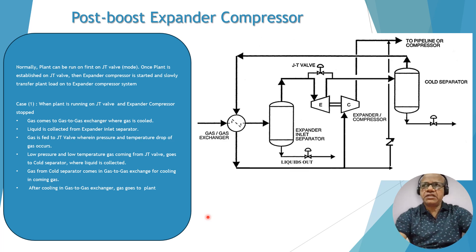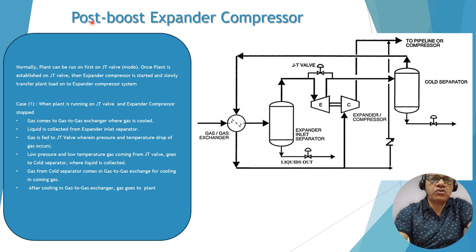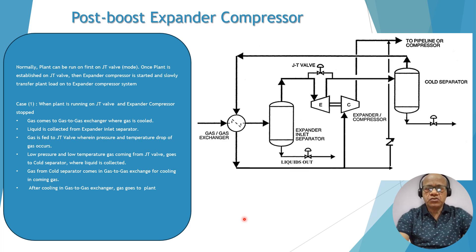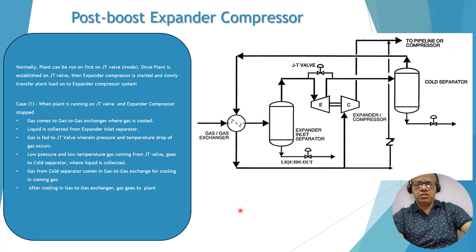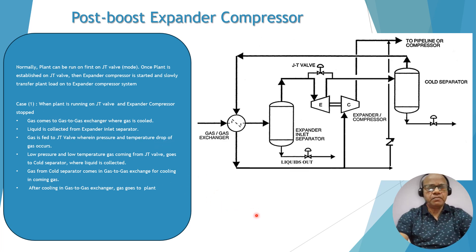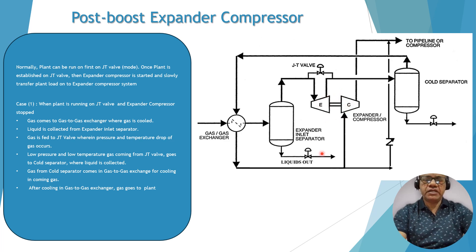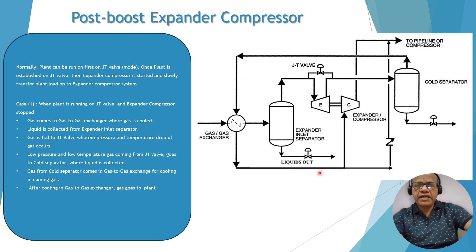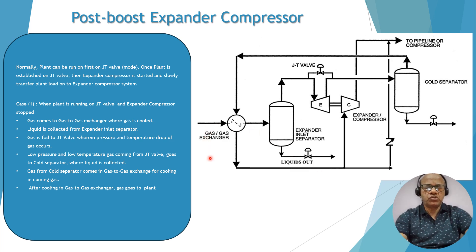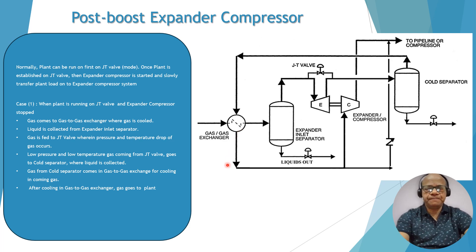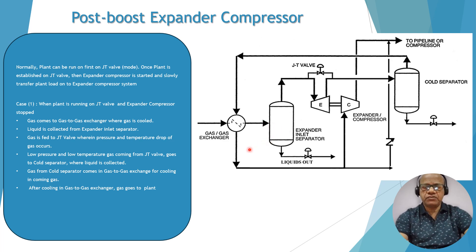Now coming to the post-boost expander compressor. Post-boost means compression of gas after the expander, and that is why it is named post-boost. Same way, the first time you have to run the plant on JT mode and then slowly start the machine on the expander. Case one: when the plant is running on JT mode and the expander compressor is isolated. Gas comes from the plant and goes to the gas-to-gas exchanger where it is cooled, then comes to the expander inlet separator where liquid is collected.